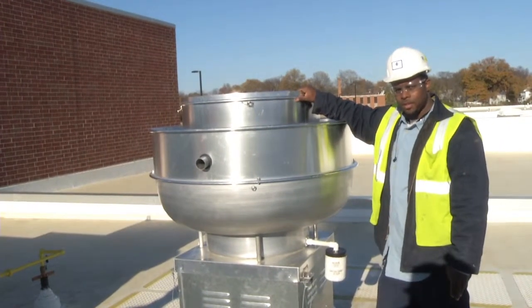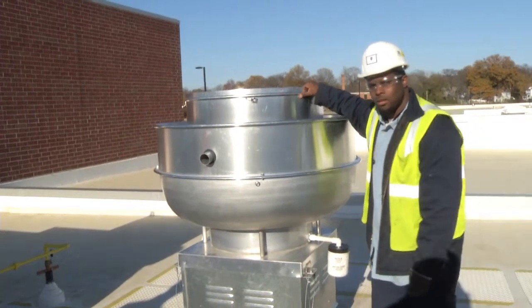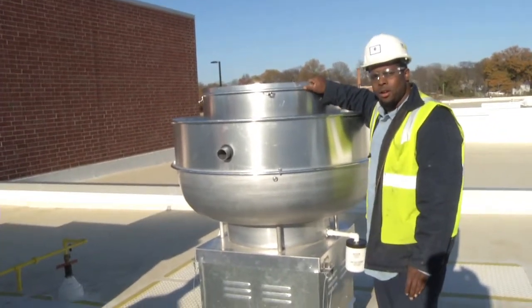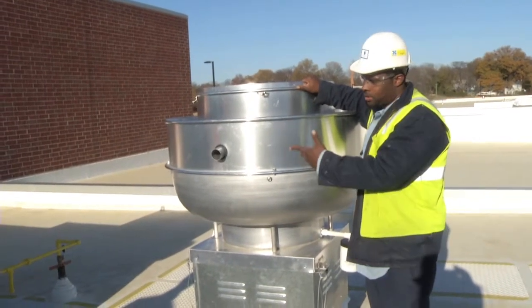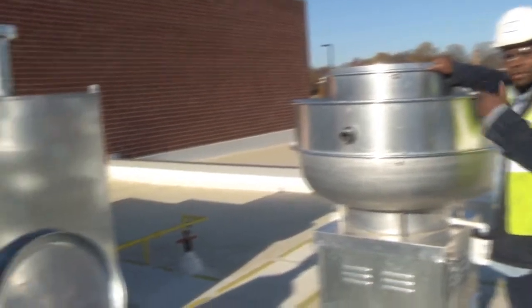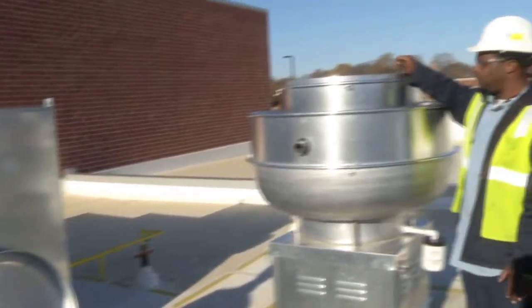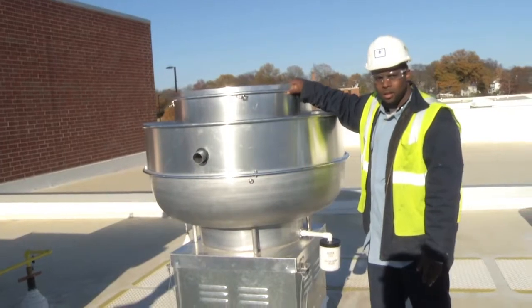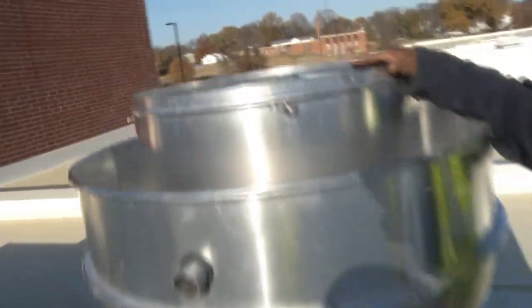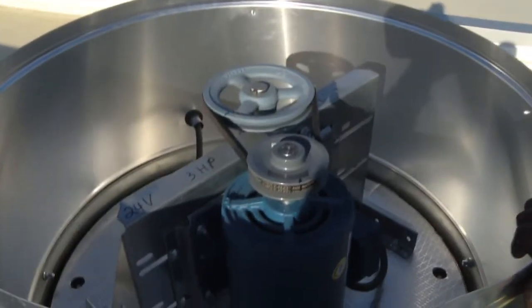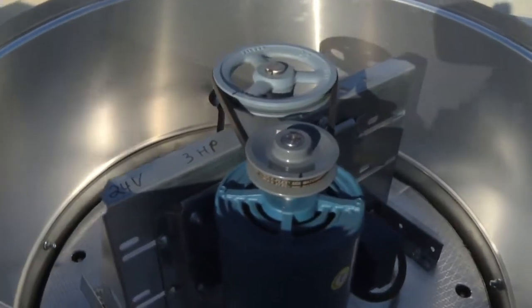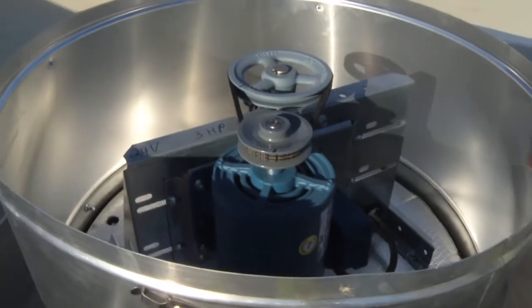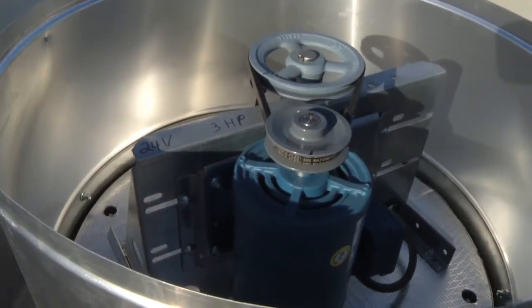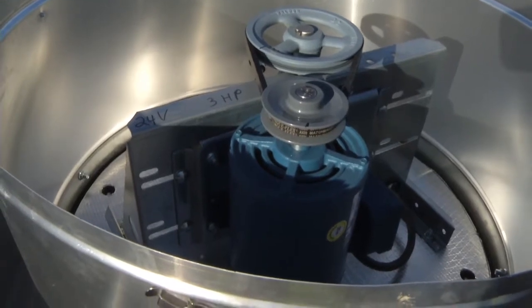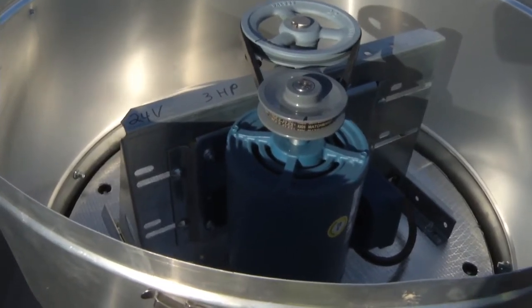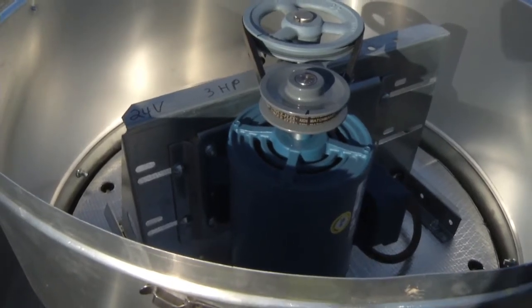Okay, this is kitchen exhaust fan 1, what we're looking at now, which is tied into the CaptiveAire kitchen exhaust, which is also tied into the makeup air system. What you have here is a 3-phase, 3 horsepower, 460 volt motor that comes on in conjunction with your exhaust hood from your kitchen exhaust. It's belt driven. You also have pillow blocks that can be greased.